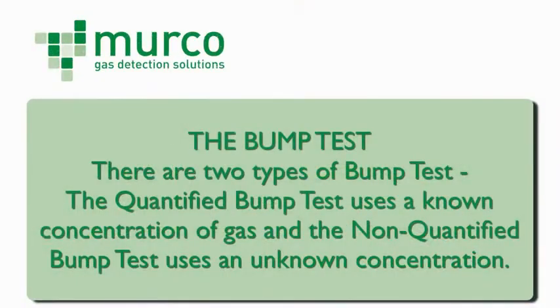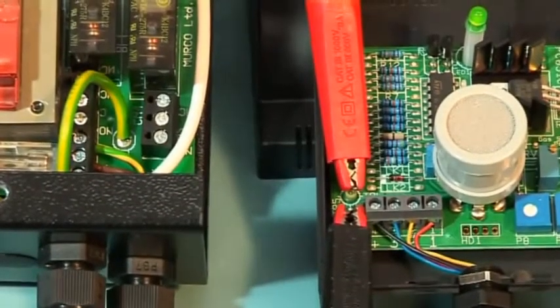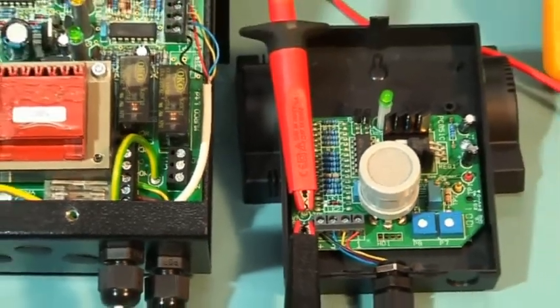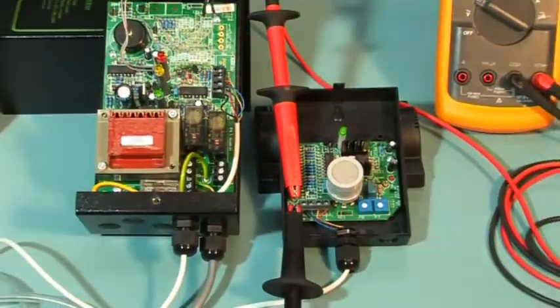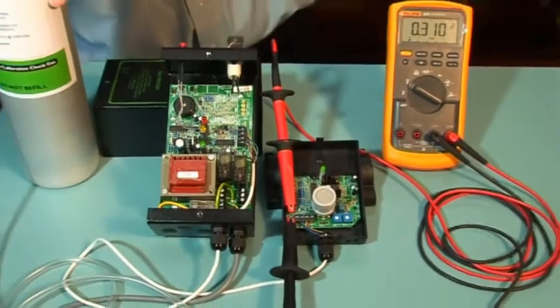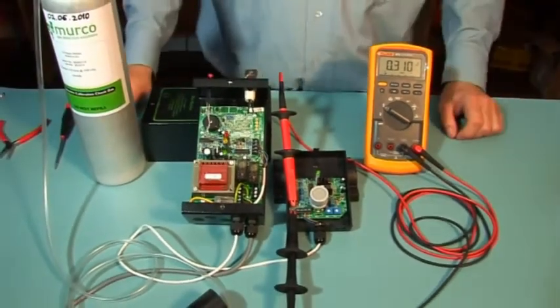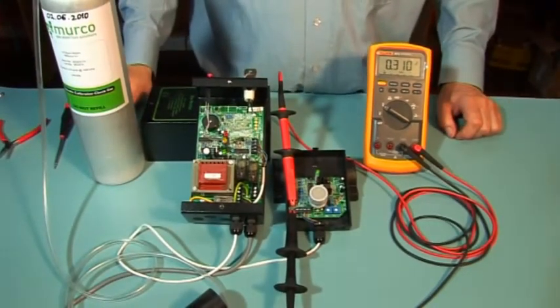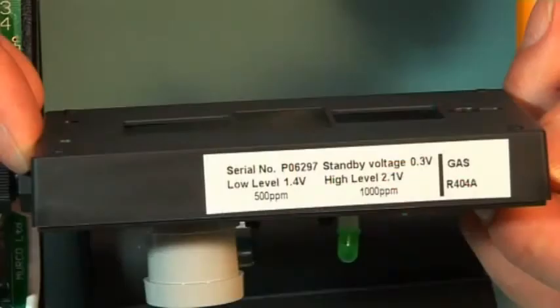There are 2 types of bump test. The quantified bump test uses a known concentration of gas, and the non-quantified bump test uses an unknown concentration. For a 2-level system, connect the voltmeter between TP5 and TP4. Once the sensor starts to see the gas, this voltage should increase. For a quantified test, you need to use a calibration cylinder for the target gas at the concentration as specified on the rating label or higher.